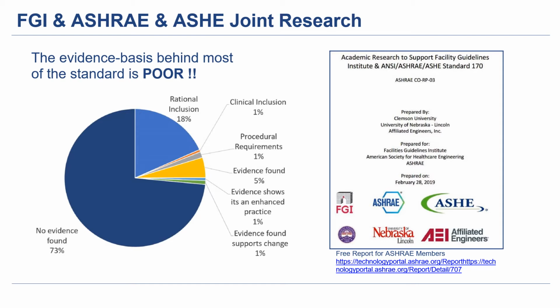We do have about 5 rooms where air quality and air movement are really important, but then we have these standards, the air change table, that cover hundreds of spaces with non-evidence-based and irrational prescriptions—4 air changes per hour in exam rooms, 6 air changes in imaging rooms. Those numbers are really completely meaningless in terms of evidence. You might as well be hanging garlic in the door frames to ward off vampires. But in our industry, we are very, very stuck in those ways.